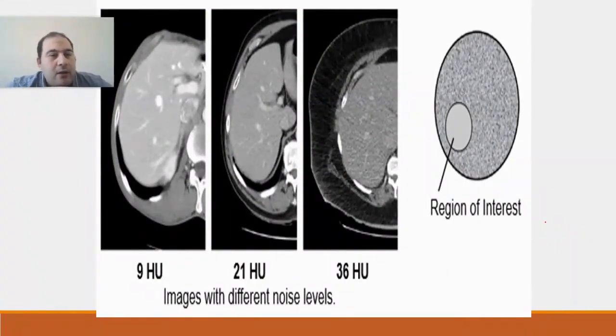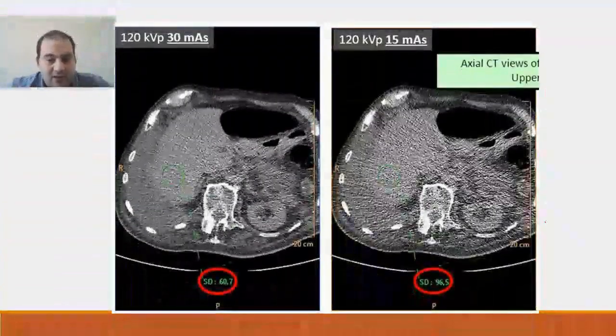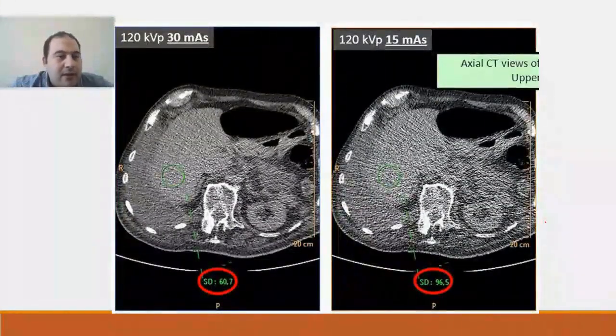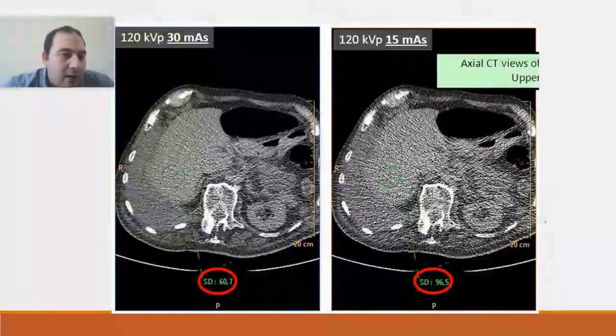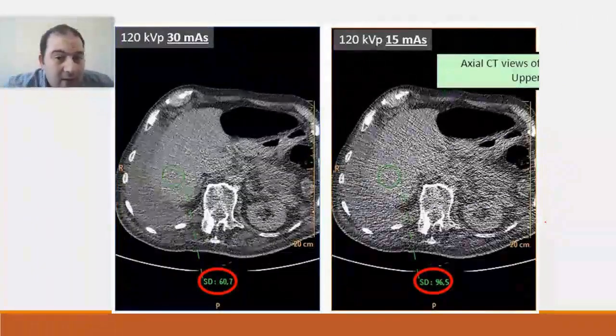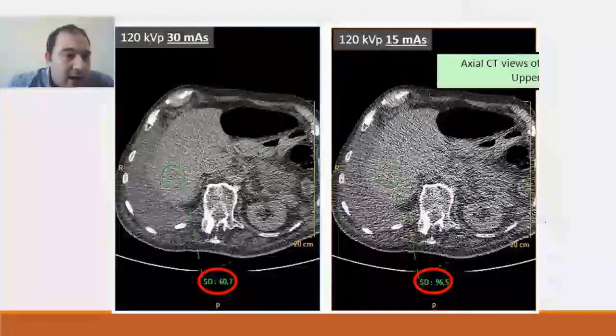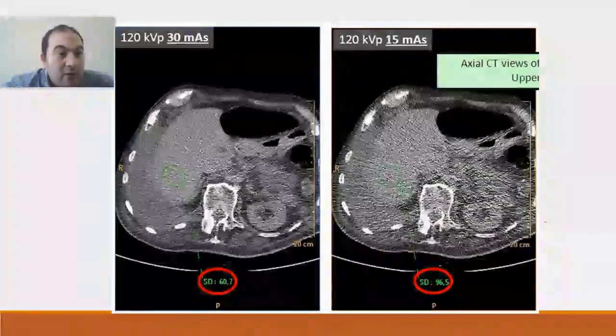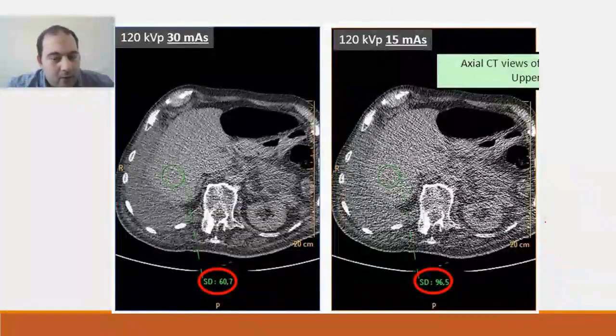When you take the region of interest on the image, it shows you the mean, maximum, minimum, and standard deviation. Normally, when you find the value of the standard deviation here, if you were to take the mean value and calculate its square root, it would not be the value that comes out. Because when we said that the number of photons should be the square root of the mean in the case of a low number of photons, if I were to talk about quantum noise, you would find that your standard deviation should be large when the number of photons is low.